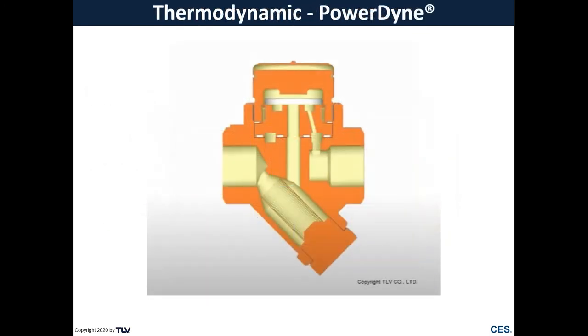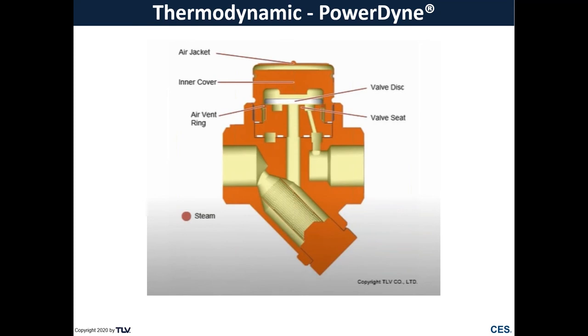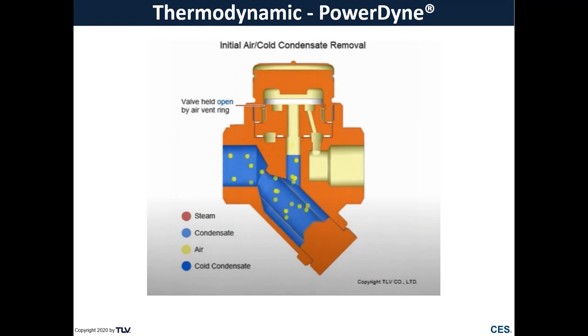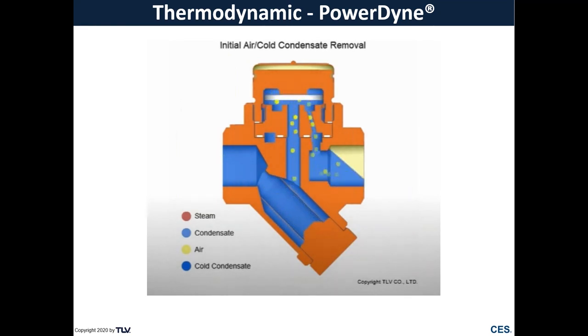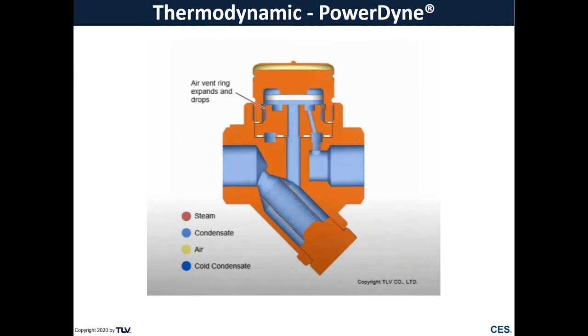We'll take a look at what that looks like inside of the steam trap. So TLV has incorporated a thermostatic element to help with startup conditions or when there's air in the system. This thermostatic element is going to hold that disc off of the seating surface, preventing it from fully closing. So this is going to help with air and cold condensate during startup. Now, once our system heats up and we start getting steam to this trap, that steam again is going to create a localized low pressure underneath that disc, pulling that disc closed. Then we get radiant heat loss, condensing that pocket of steam on the top side of the disc, and it will then cycle again.